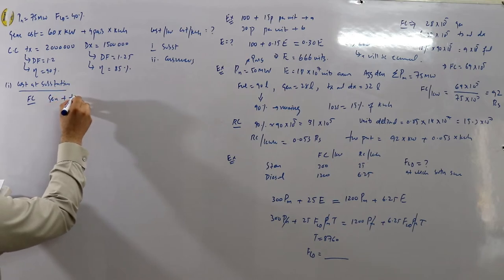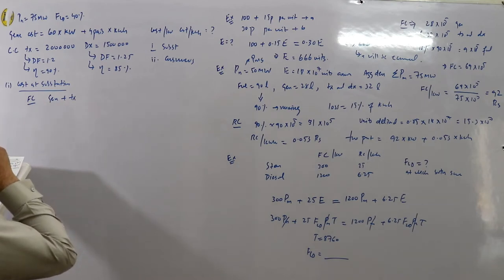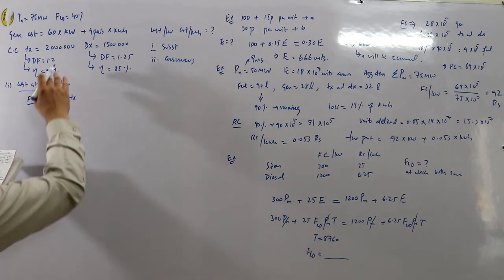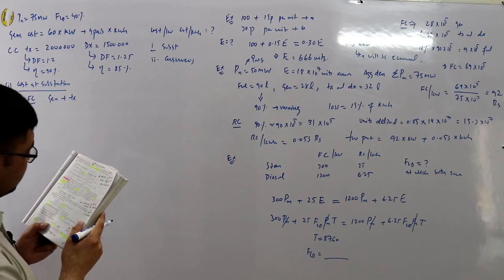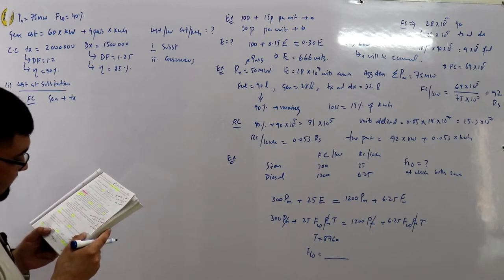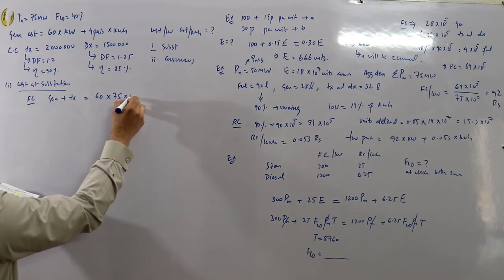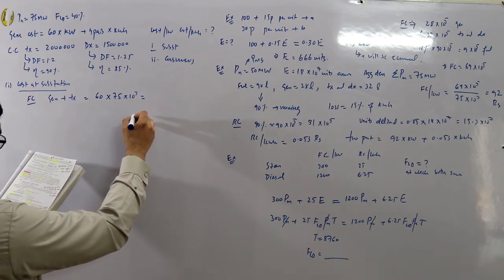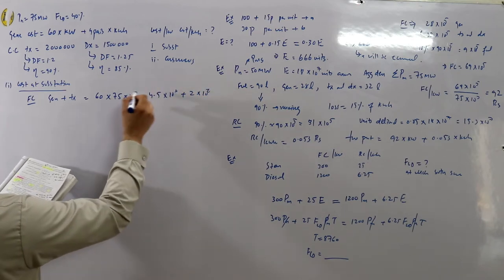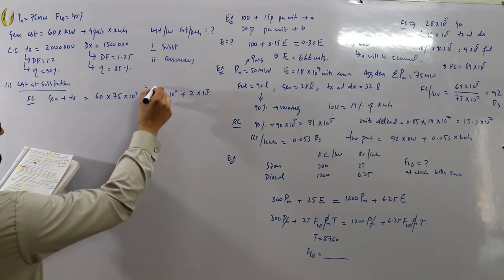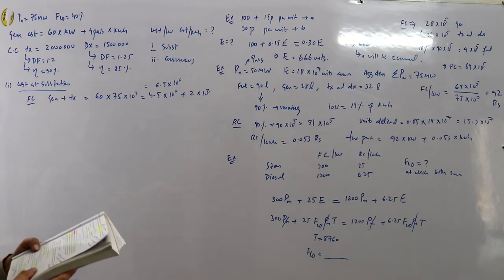At the substation: fixed charges include generation cost plus transmission cost. Generation cost = 60 × 75 × 10³ = 4.5 × 10⁶ rupees. Add transmission cost of 2 × 10⁶. Total fixed charges at substation = 6.5 × 10⁶ rupees.